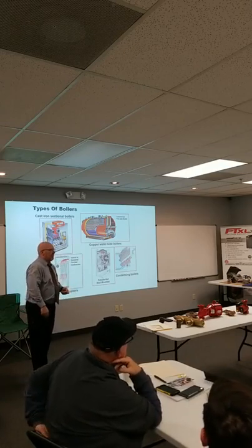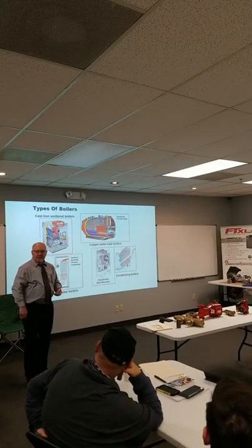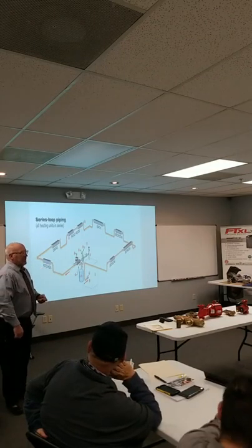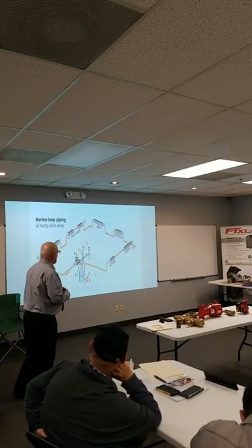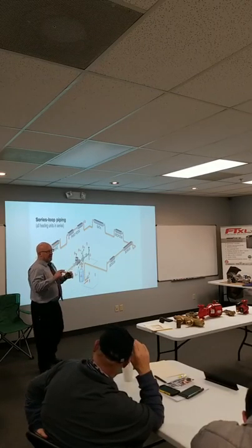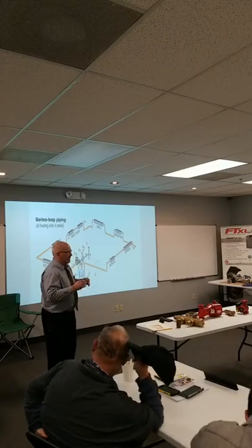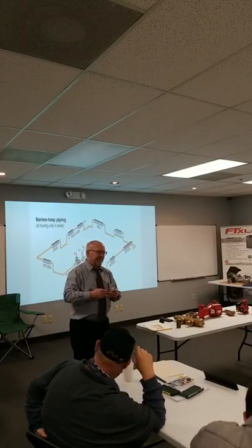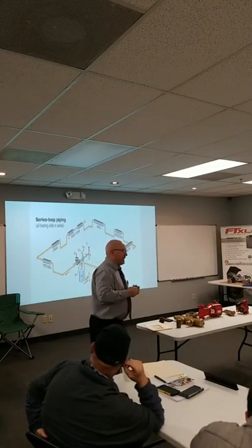But we only condense when we bring back low return water temperatures. And how low? The lower, the more efficient. How low can we go? We're going to see that in a minute. So, okay, we'll talk about it because it came up. Flue gas condenses at about 135 degrees. So if our water temperature's coming back at 135, we're going to start condensing flue gases.